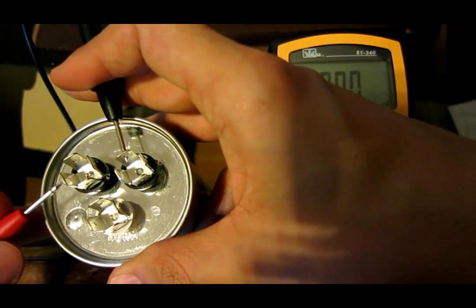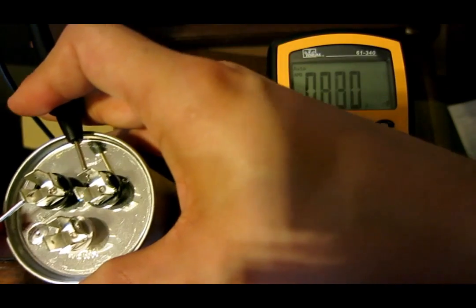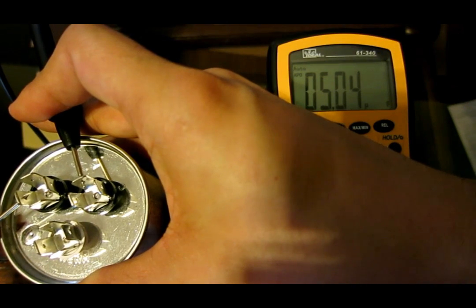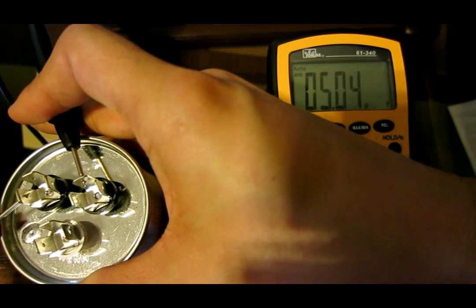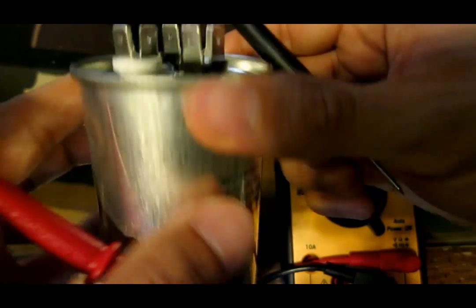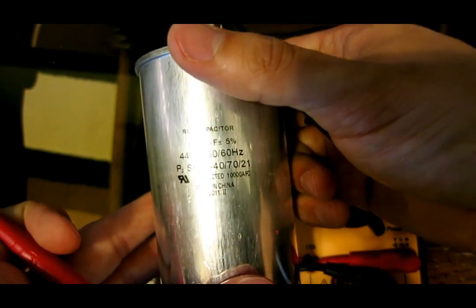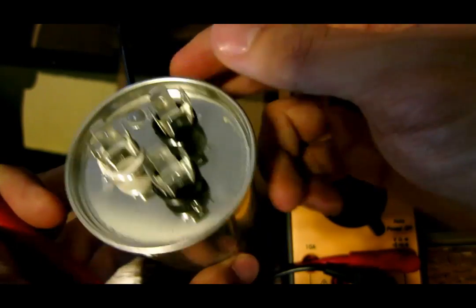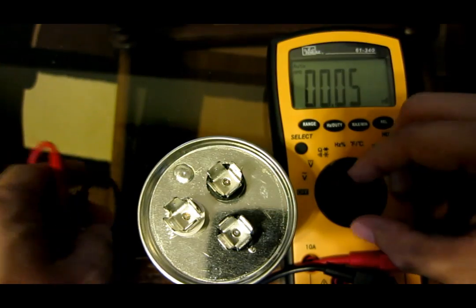And then if I measure the fan, it should say 5. There you go. 5 microfarads. Basically how you measure capacitance on your run capacitor. And good luck replacing it.